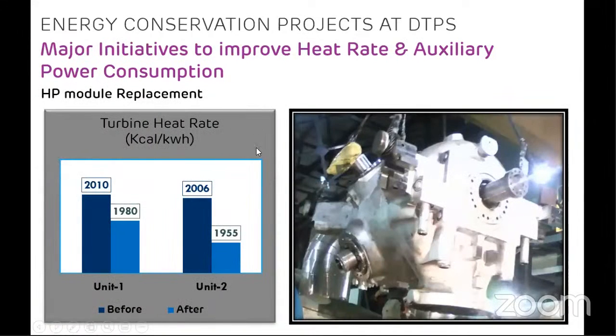And the next maintenance practice you can say is that during every overhaul, we replace the HP turbine module in our plant. So for unit 1, the heat rate was 2010 kilocalories per kWh before overhaul. After overhaul, when we replaced the HP turbine module, this heat rate changed from 2010 to 1980 kilocalories per kWh. Similarly, in the second unit, it changed from 2006 to 1955. All these are in kilocalories per kWh. So this is a huge saving we are gaining by HP turbine module replacement during annual overhauling.